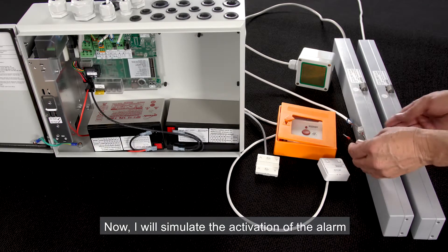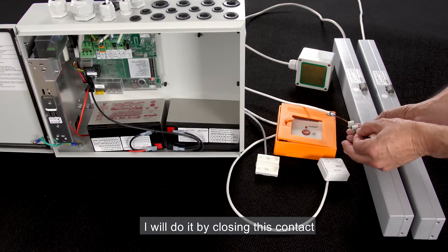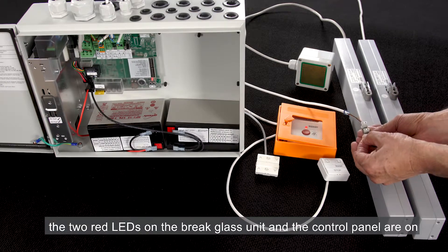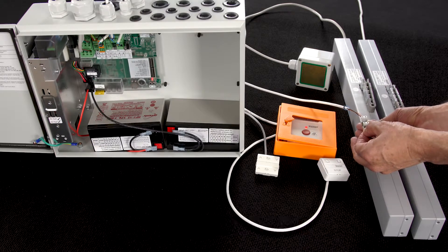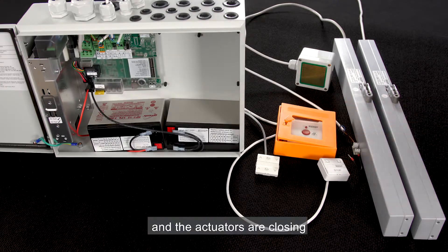Now I will simulate the activation of the alarm from the fire alarm system. I'll do it by closing this contact. Again, the two red LEDs on the break glass unit and the control panel are on, and the actuators are opening. When I open the contact, the red LEDs turn off and the actuators are closing.